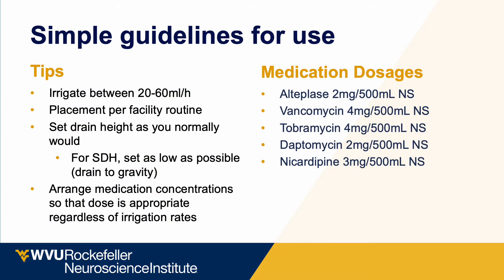At WVU, we've been early adopters of the IRRAflow system. I use it aggressively for any clinical scenario where an EVD would be used. I suggest irrigating between 20 to 60 mLs per hour. Placement can be per facility routine — here we often use a bedside stealth machine, but ultrasound, OR, or standard anatomic techniques all work fine. Drain height should be set as you normally would, and for subdural hematomas, set it as low as possible, equivalent to draining to gravity. Arrange medication concentration so the dose is appropriate regardless of the irrigation rate.